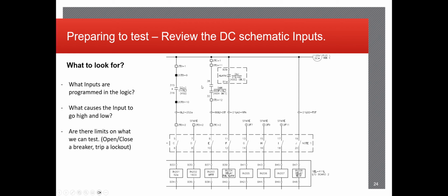In this case, we can discuss the possibilities of messing this up again, because if you were to operate this lockout, for example, right here, this 5AH lockout, if you were testing it all the way up to input 203 in the relay, that lockout could be connected to two or however many other pieces of equipment. So you want to make sure that lockout is properly isolated and that you test it with the isolation points from every other possible contact.